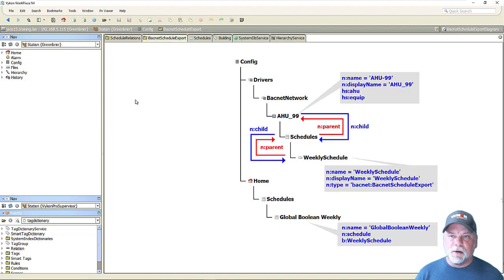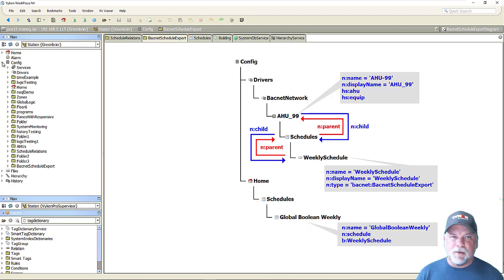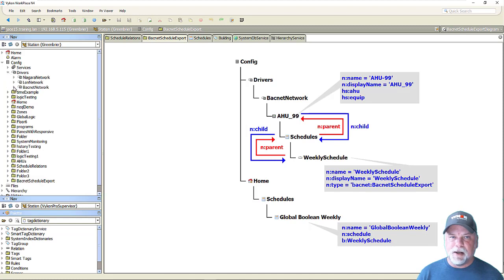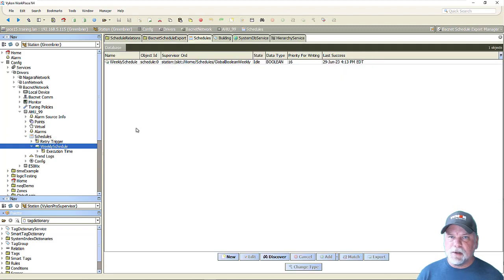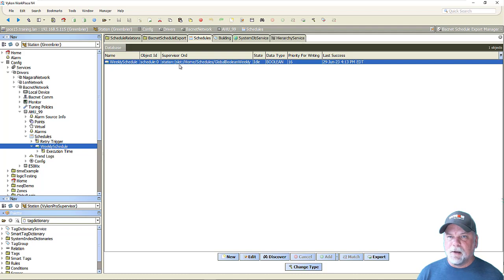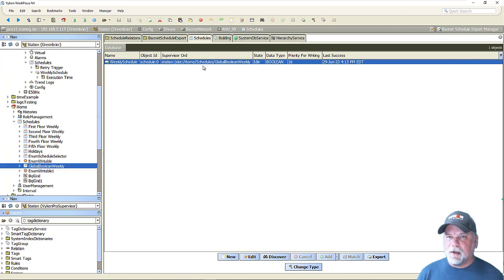Now in this video, I want to focus on BACnet schedule exports because BACnet schedule exports are similar to the Niagara schedule exports, but it's a little different from where we might have an actual schedule linked to a control point. In this case, we have a BACnet device and that BACnet device has a schedule device extension, and then there's a schedule export underneath that. Looking at that in the nav tree here, we can see under the drivers and the BACnet network, AirHandler 99, there's a schedule device extension and this is the exported schedule. Looking at the schedule device extension under AirHandler 99, we can see that I'm exporting this schedule from the home folder — under the schedules folder, there's this global boolean weekly schedule — and that's being exported from the station to the BACnet device to this schedule object.